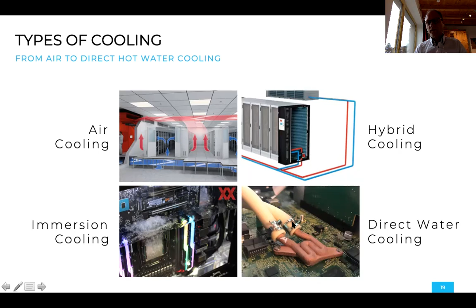New technologies evolve, like immersion cooling, where you basically dump the whole server in a non-conducting liquid and cool it with this. So it has really some advantages, but there are also complications, in that it's quite expensive. And there are solutions out there that have been developed over decades now, and we've picked up this development and brought it further to direct water cooling, meaning you bring a cooling loop to the CPU, to the chips, and you pipe the water across this cooling infrastructure, across this heat exchanger, and very closely to the chip, you extract the heat. And that's basically the secret of what we are doing: extracting the heat directly from the CPU.